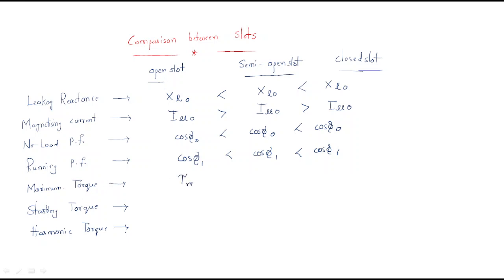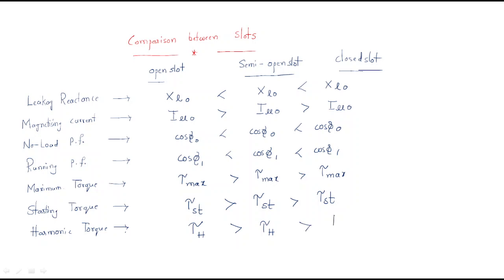Maximum torque is inversely related: open type slot has the most maximum torque, compared with semi-open, compared with closed — which has the least. Starting torque follows the same pattern: open type slot has the most starting torque, then semi-open, then closed type has the least. Harmonic torque: for open type slots flux distribution is non-uniform, so harmonic torque is high. It decreases from open to semi-open to closed type slots.